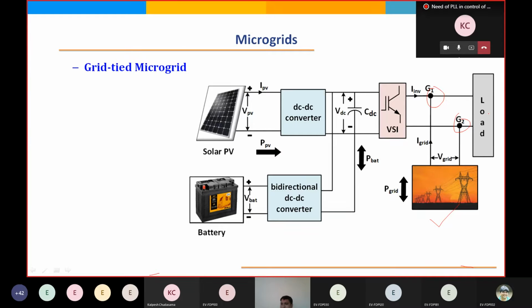So let's say the load requires 10 kilowatts of power. PV will supply 5 kilowatts, battery supplies 5 kilowatts, fine, the grid does not need to supply. Now the load requires 20 kilowatts: the PV gives 5 kilowatts, the battery gives 5 kilowatts, and the grid has to supply 10 kilowatts. If PV is generating 10 kilowatts and the load requires 5 kilowatts, 5 kilowatts can go to the load, and 5 kilowatts can be fed back to the grid, or it can be used to charge the battery. So different scenarios will arise in this.